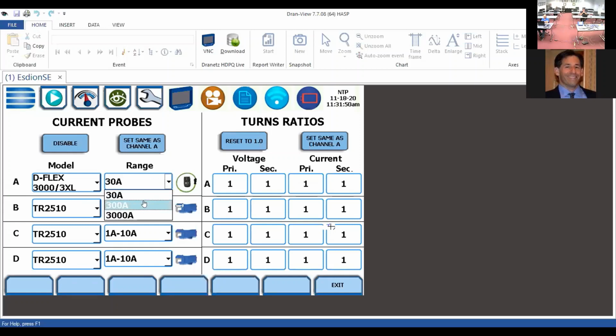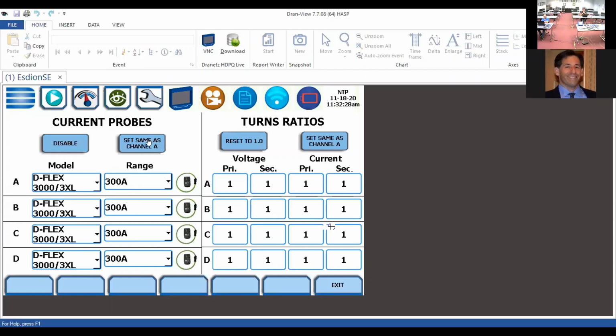So this is what you have to tell the instrument. On the probe itself, on the integrator, it has a range selector switch. You want to make sure that whatever range you have selected on the integrator matches the selection here. So in this case, I'm going to select 300 amps. And then here, as a shortcut, you could do the same function the long way for each of the remaining channels, or you can simply use the shortcut here and it sets them all the same. That's a way to quickly get through a setup.